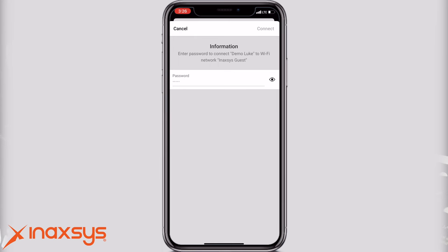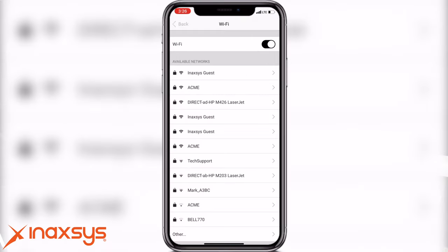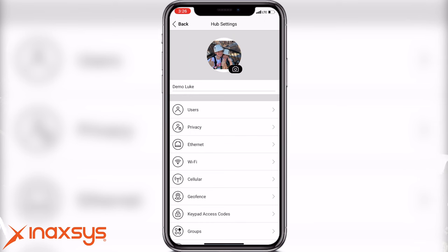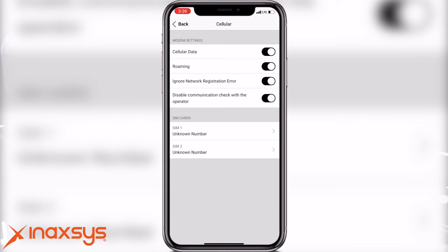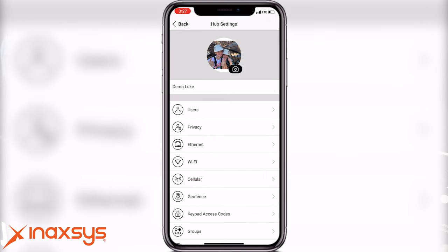You can then disconnect the panel from the Cat5 cable if you only want it communicating over Wi-Fi. A common problem, though, is that if we have the panel connected over Wi-Fi and change from one provider of internet services to another, this causes a problem because your panel hasn't been learned into the new network. There are two ways to fix this. The first is to once again connect the panel via an Ethernet cable to the new router and learn it into the new Wi-Fi network. The second is if you have a cellular communicator — by clicking on cellular, you can see the two SIM cards, see if it's roaming, see what network it's on. If it is connected to a cellular network, you can log in via cellular and relearn it into the new Wi-Fi.